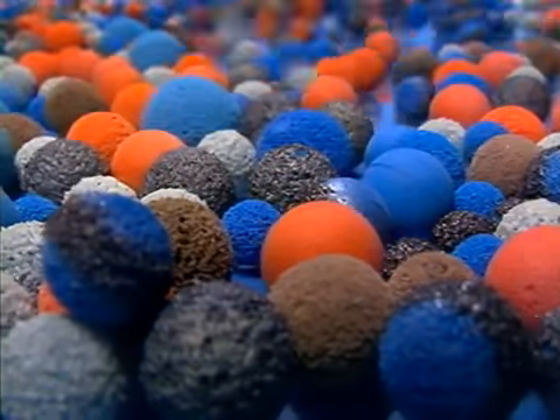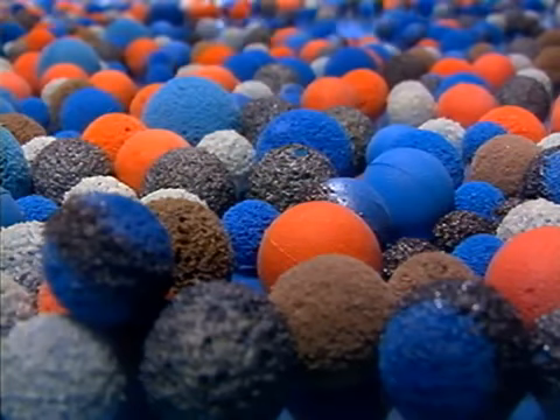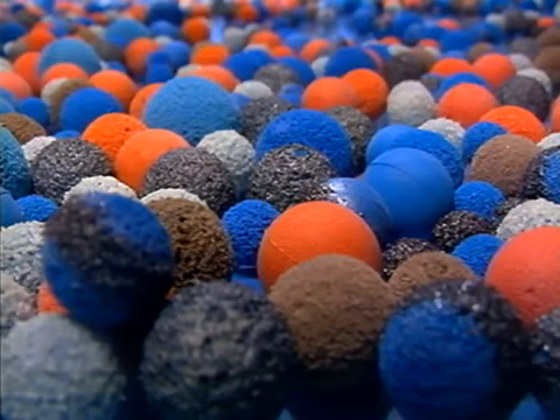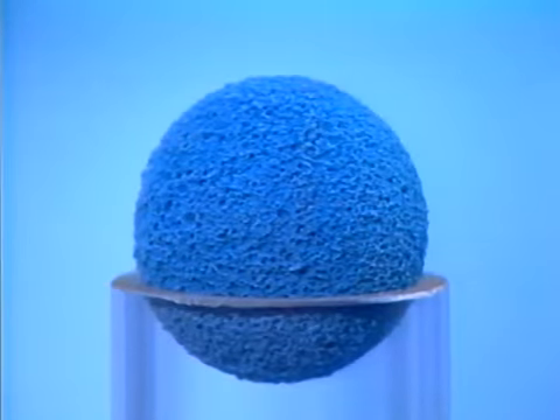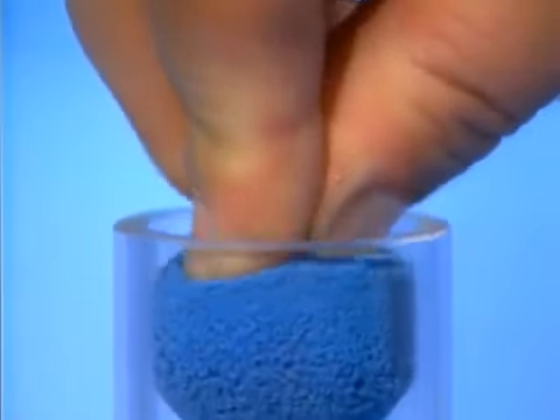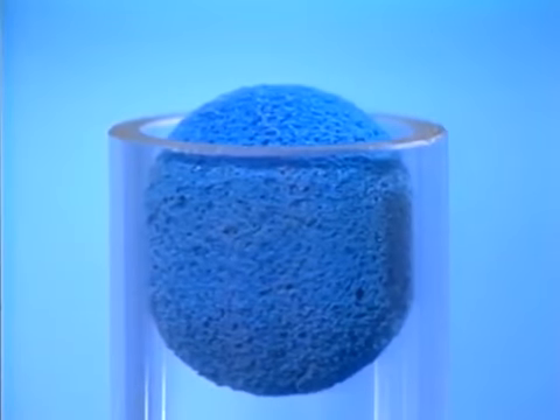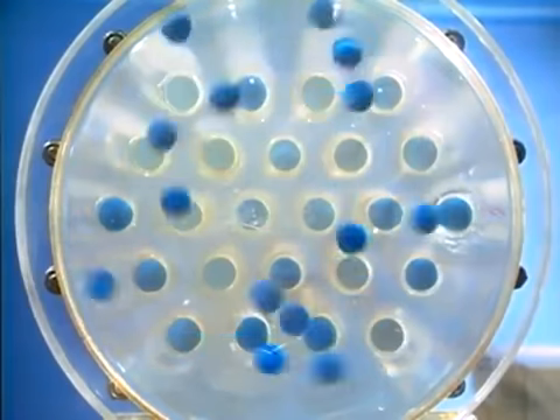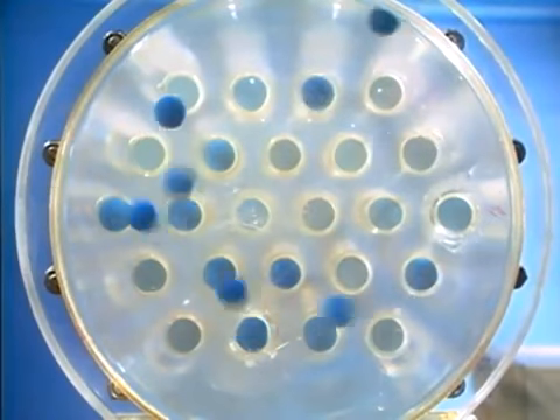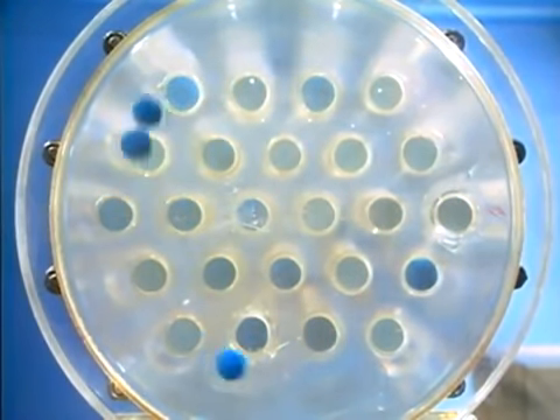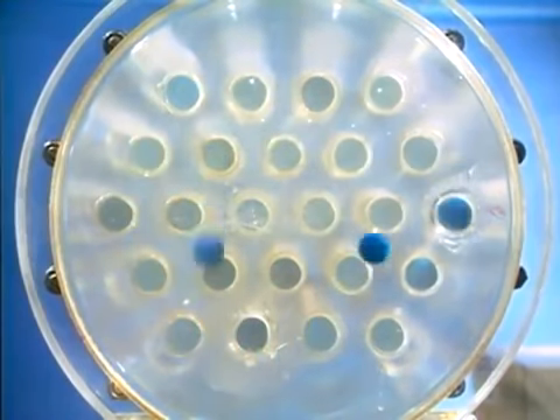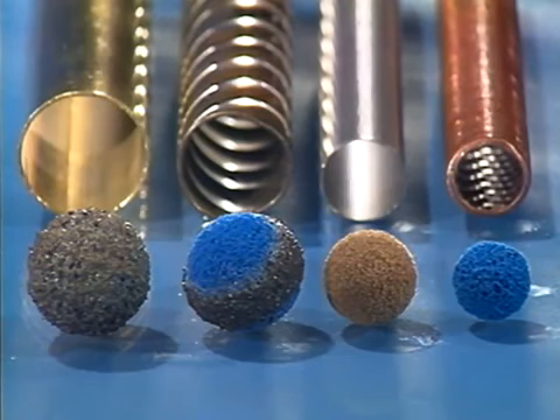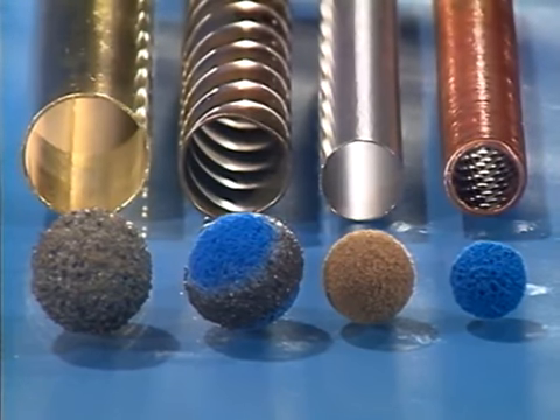To do their cleaning job and keep power stations operating efficiently, the sponge rubber balls must meet specific basic parameters. The balls must be oversized compared to the tube internal diameter. The balls must be thoroughly distributed at the cooling water inlet to ensure they reach all parts of the condenser tube nest. The ball diameter and hardness must be matched exactly to the individual condenser tubes.